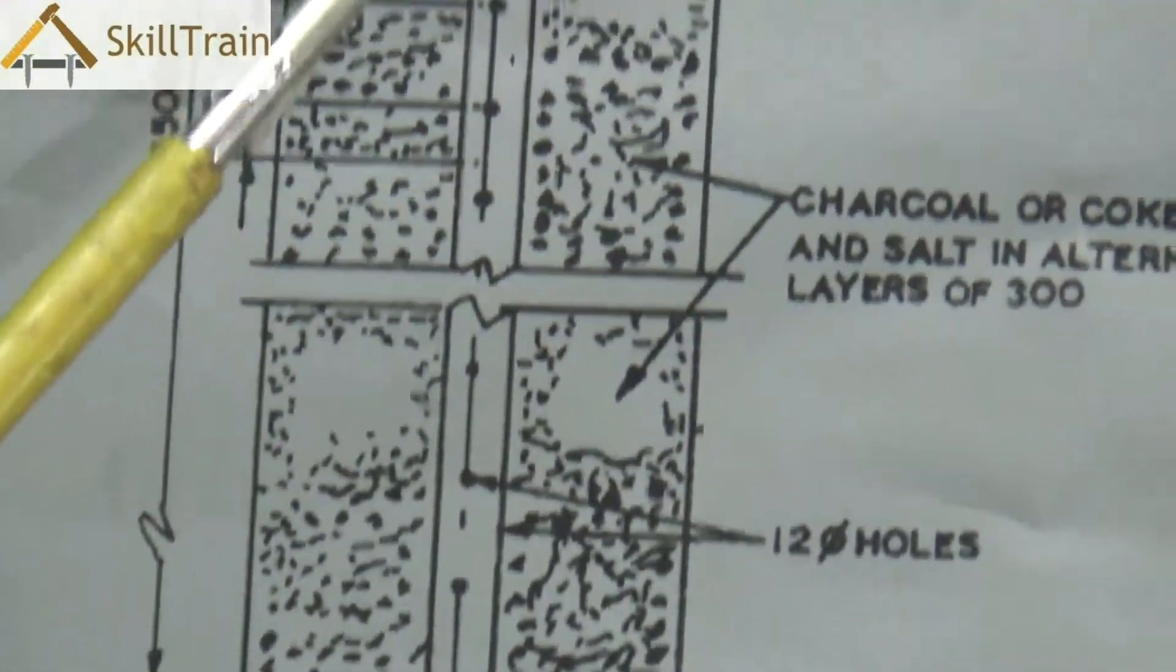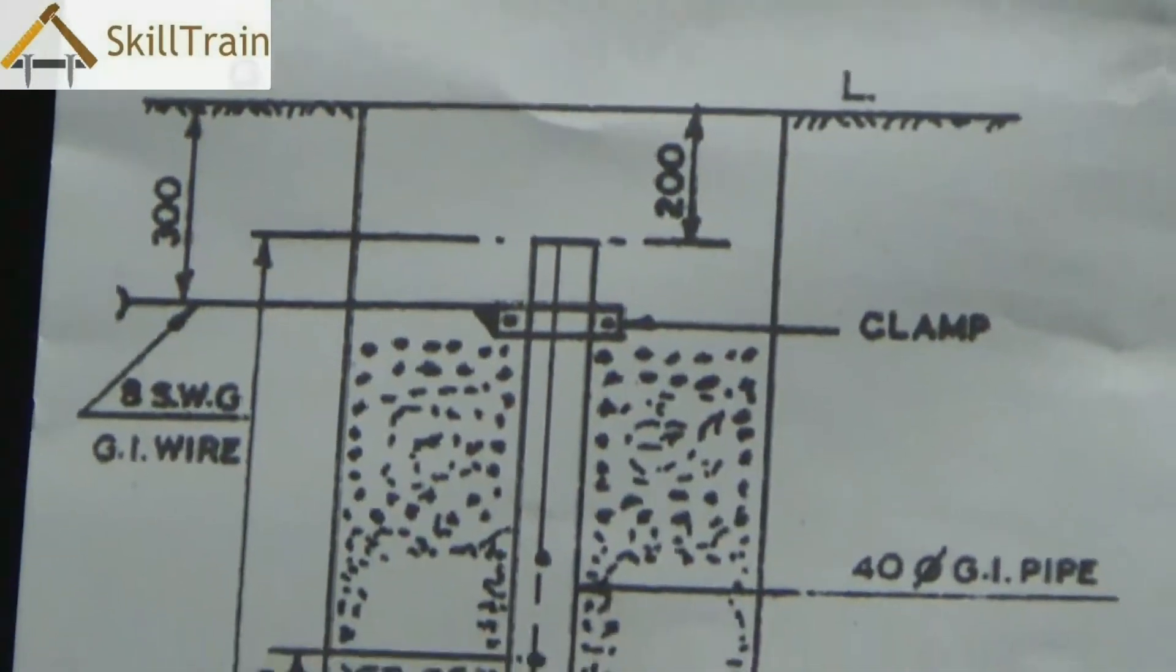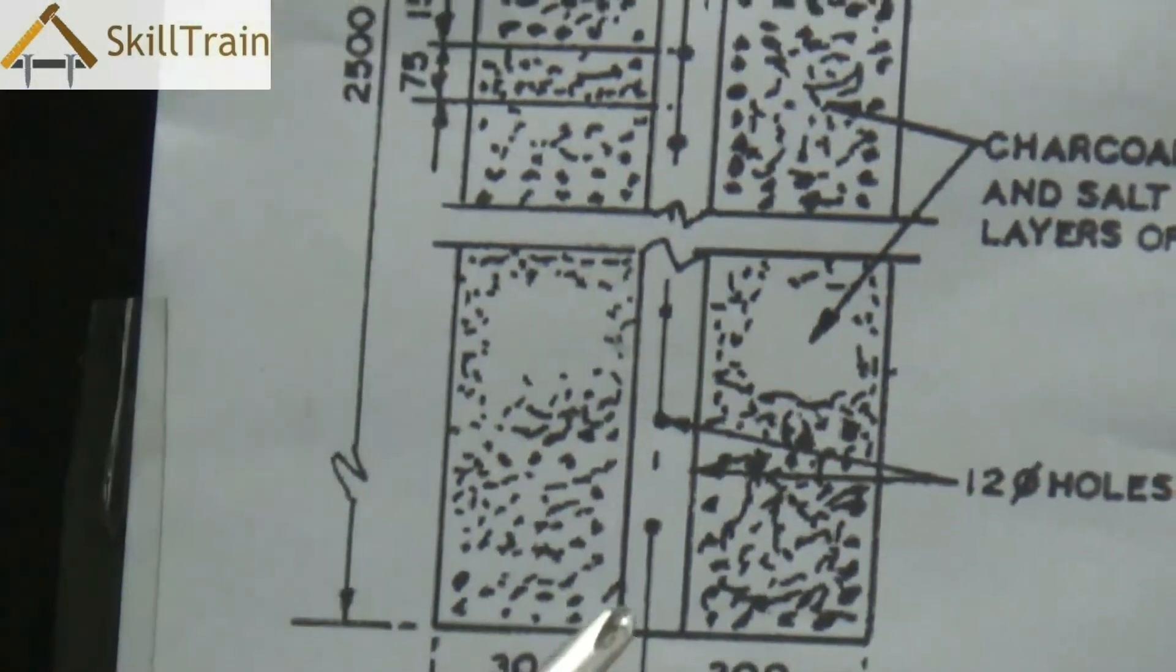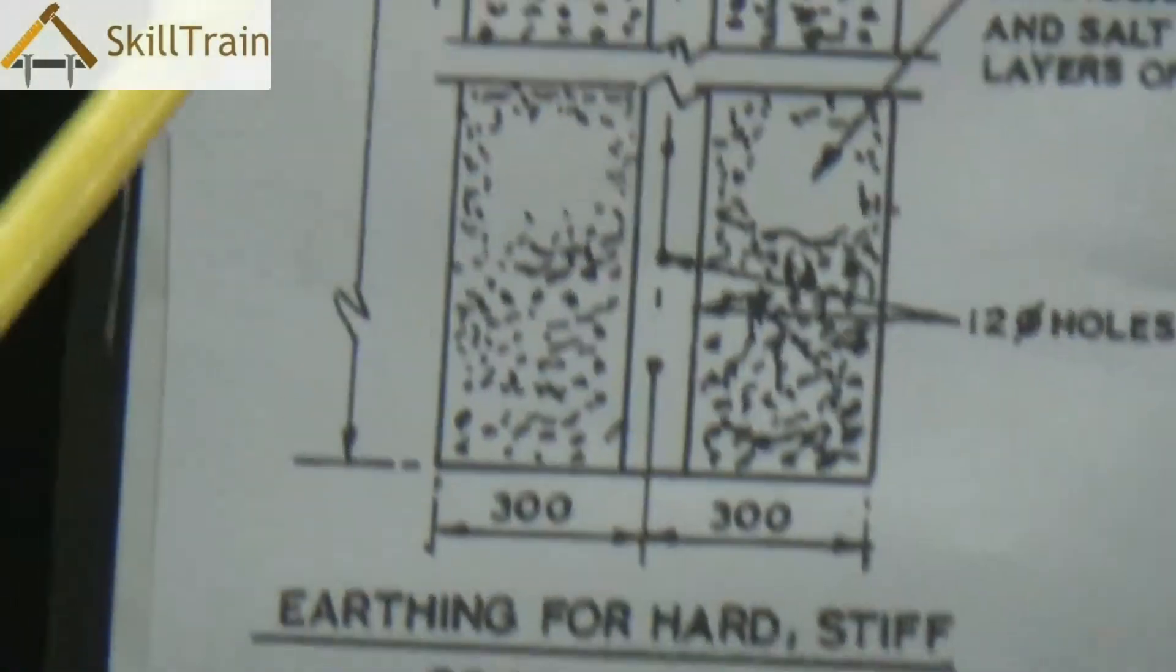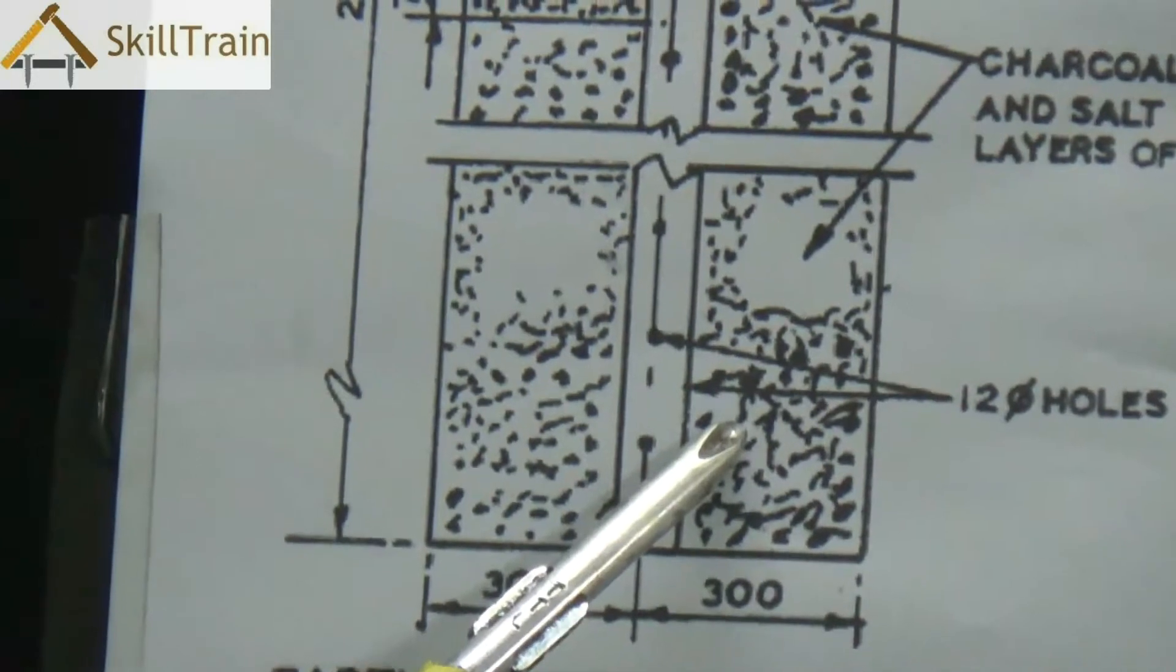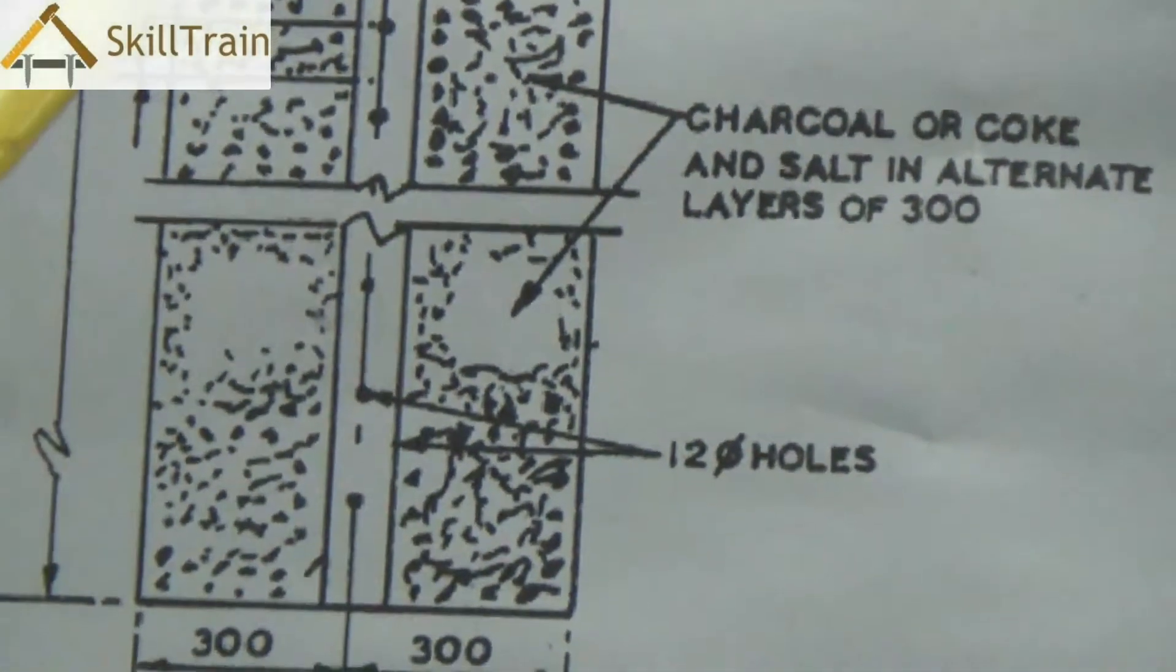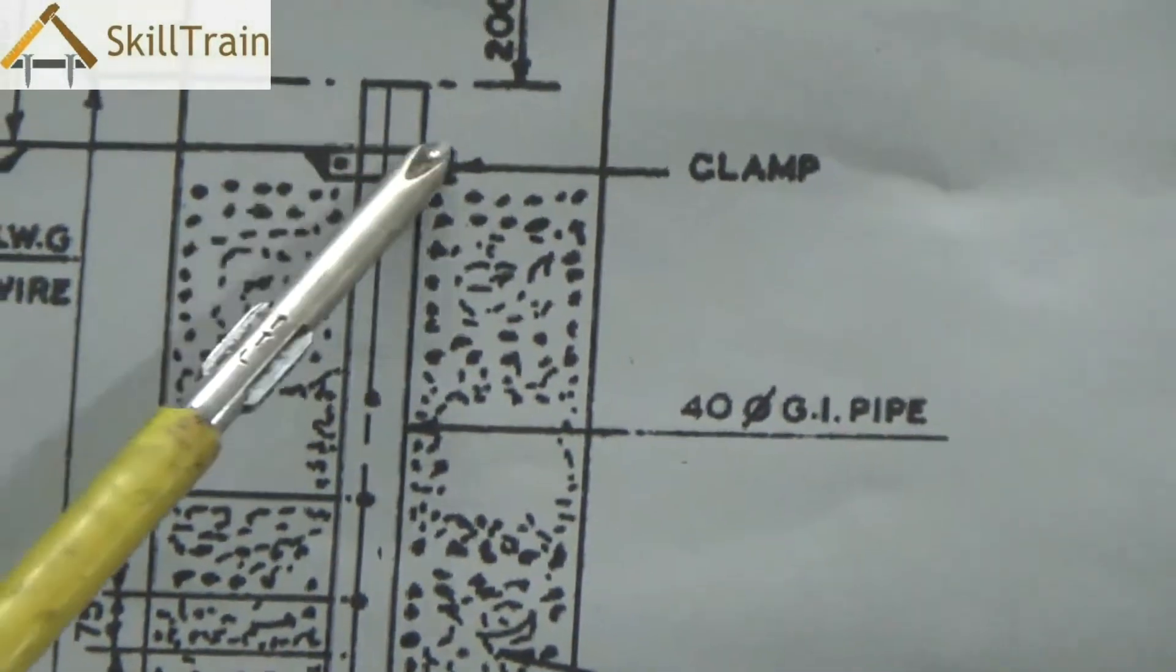The other type of soil is hard soil, and in hard soil you will need to place salt and charcoal mixture because there is no moisture. The charcoal essentially maintains the humidity or increases the conductivity, and salt as an ionic solution reduces the resistance to the dissipation of electricity.